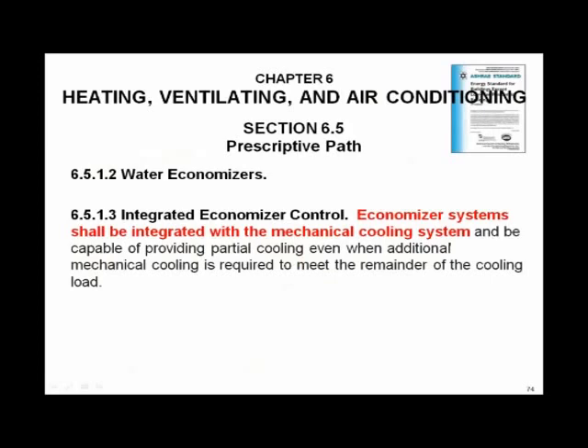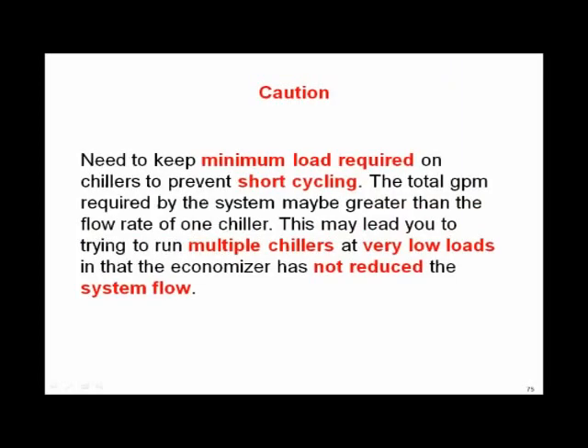So this integration thing popped up, and I spent some time on it. Here's the wording again, and it very clearly states to provide partial cooling with the water side economizer, even when additional mechanical cooling is required. That's the key thing. That's the huge change you've got to deal with. I caution you about the possibility of short cycling when you do that, because your total flow rate to your load in your building has not changed, but you're reducing the return chilled water temperature going back to the chiller plant. As the wet bulb goes down, you're able to take more and more of that with the water side economizer, and you may wind up short cycling your chillers if you're not careful.